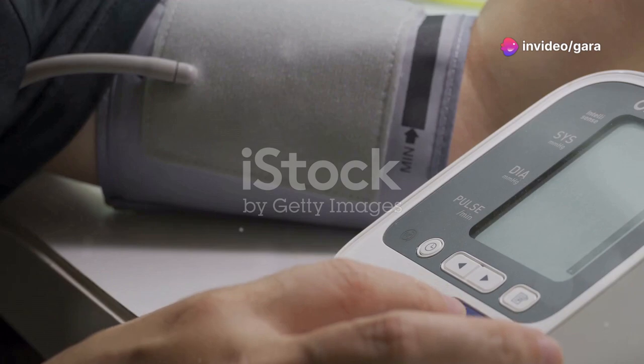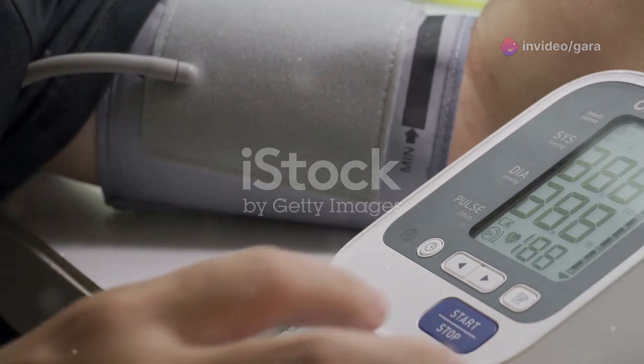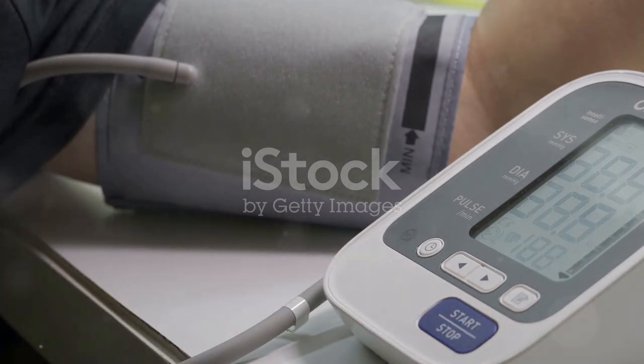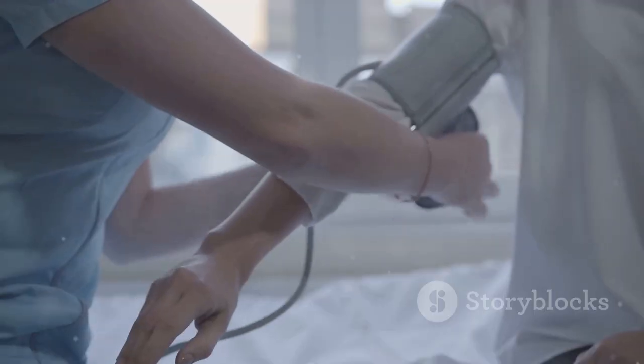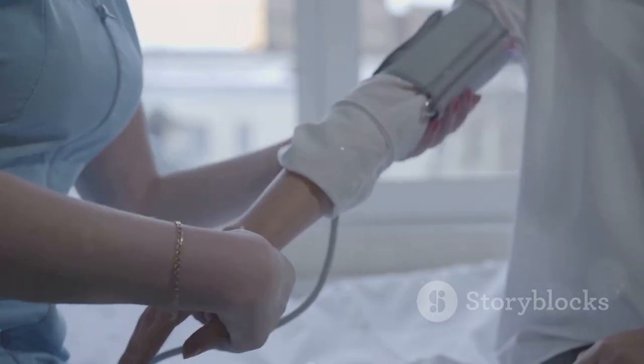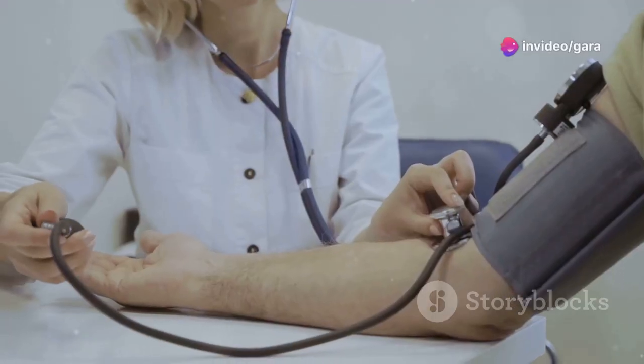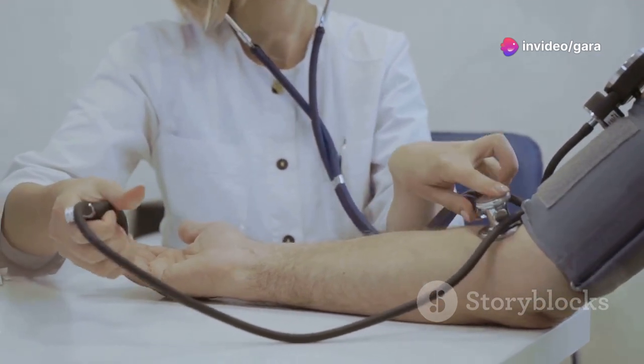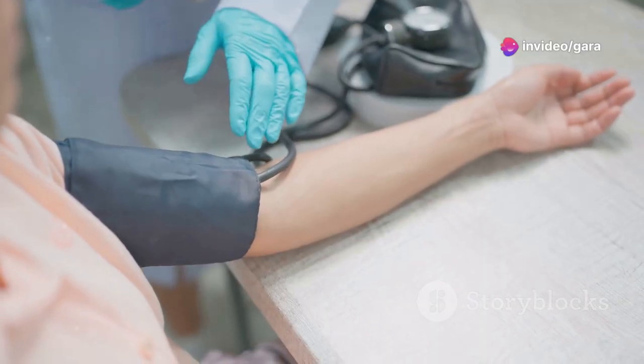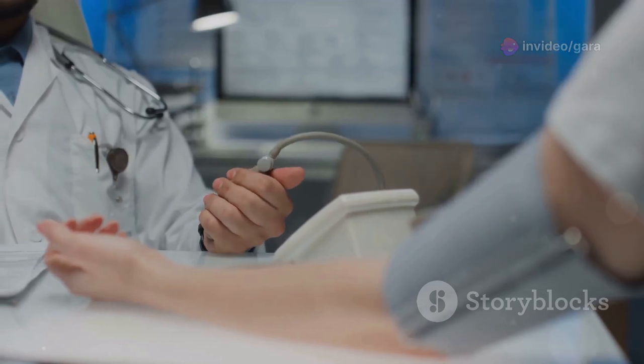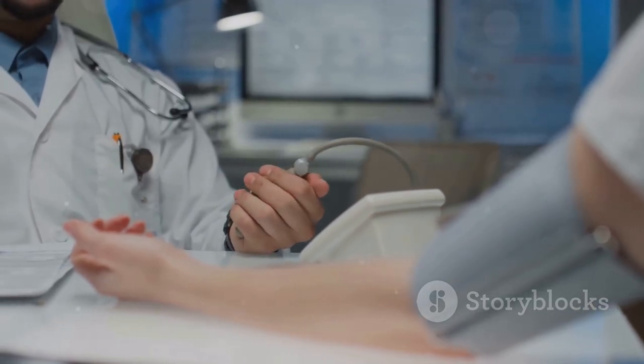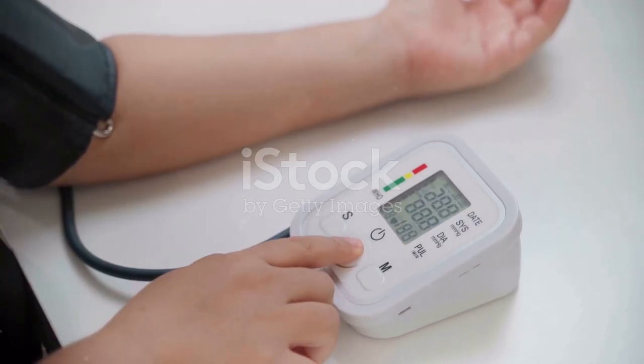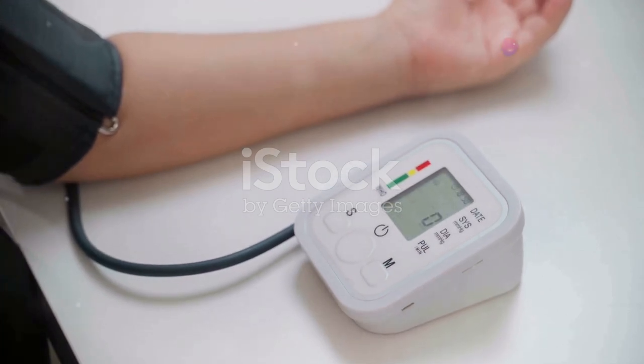First things first, let's break down the components involved: a pump, a valve, and a pressure sensor. These three work together to give you accurate readings of your blood pressure. So, how does the oscillometric method actually work? Imagine you have a cuff wrapped around your arm. The process starts when the pump inflates the cuff, squeezing your arm tightly. This inflation temporarily stops the blood flow in the brachial artery.